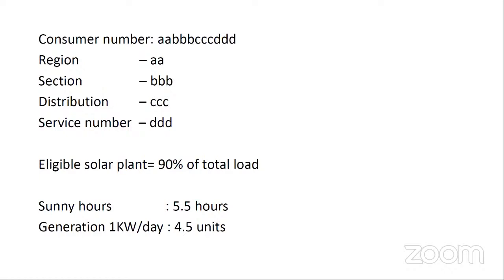So 90% of the total load is no longer the rule, it is now 100% of the total load. If you have a 10 kilowatt load, you can put a 10 kilowatt system, but not more. You cannot put 11, but if you want to put 5 or even 2, you can, since it's less than your sanctioned load.